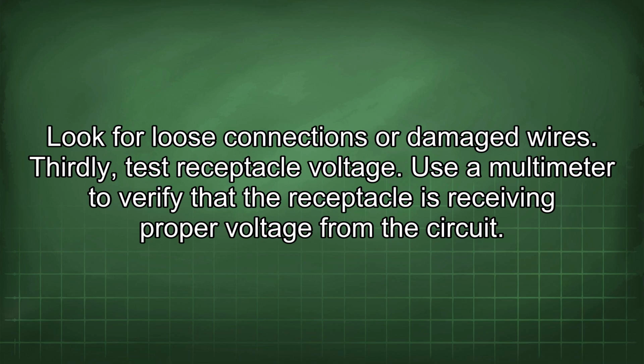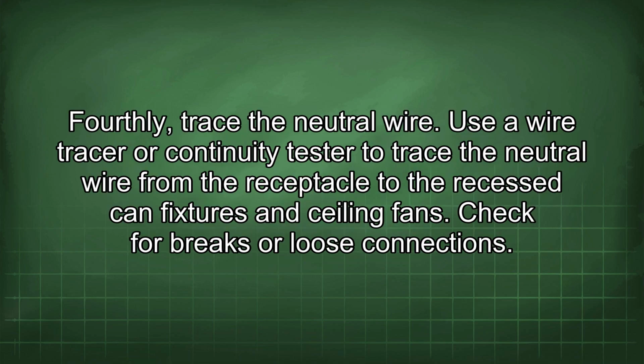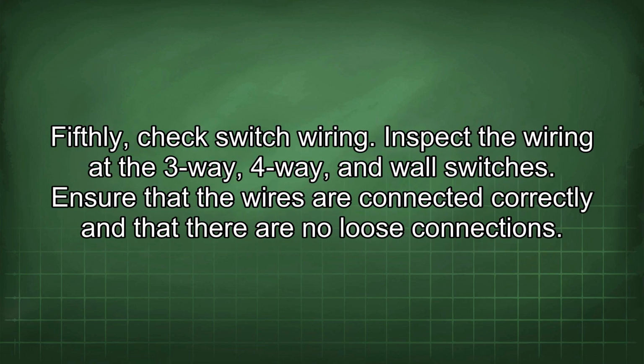Thirdly, test receptacle voltage. Use a multimeter to verify that the receptacle is receiving proper voltage from the circuit. Fourthly, trace the neutral wire. Use a wire tracer or continuity tester to trace the neutral wire from the receptacle to the recessed fixtures and ceiling fans. Check for breaks or loose connections. Fifthly, check switch wiring. Inspect the wiring at the 3-way, 4-way, and wall switches. Ensure that the wires are connected correctly and that there are no loose connections.